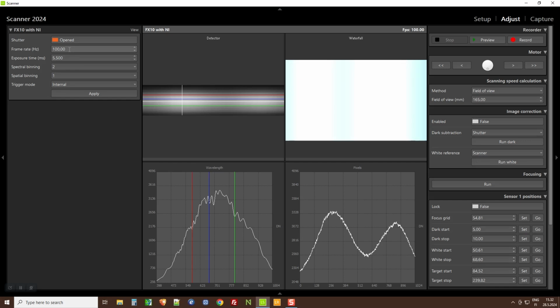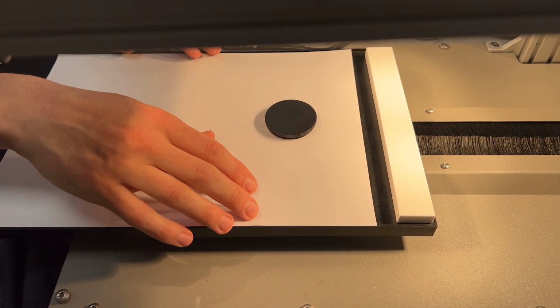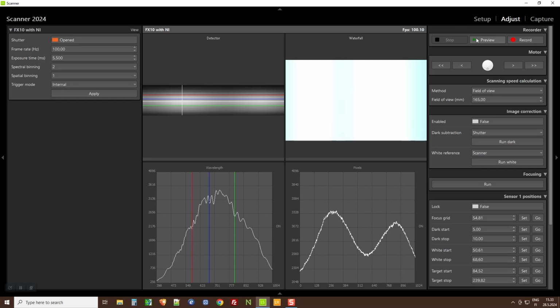So integration time is now adjusted. Then you could think about the frame rate. Now we have an exposure time which is at about 5.5 milliseconds. So theoretically, the maximum frame rate you could use is 1 divided by about 6 milliseconds. So here I was thinking to use 100 frames per second, because it means that you acquire a frame every 10 milliseconds. That means that there is time between frames for the camera to handle the next one. So I think this is a good one, but you can change it from here. There is one aspect that now you have to take into account. This is the scanning speed. And to adjust it, basically, I take a sheet of paper like this, and I put a black circle at the top of it. And then I can make a preview.